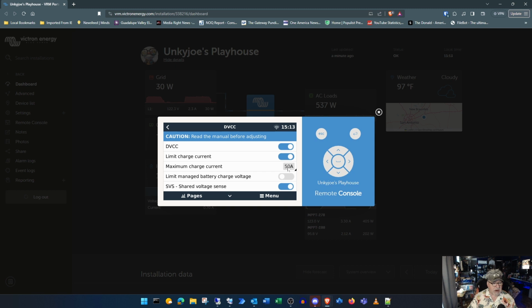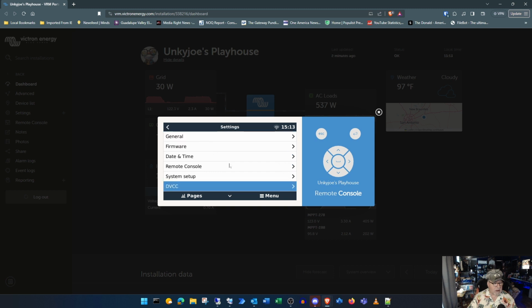I had this set up, I think to 70 or 80 amps, 70 amps to the maximum, and it blew the fuse. Because keep in mind, this inverter also has to power other things while it's charging your battery. So I lowered that down to 50 amps, and that is an okay current to charge at according to the manufacturer. But then there's this ESS setting.